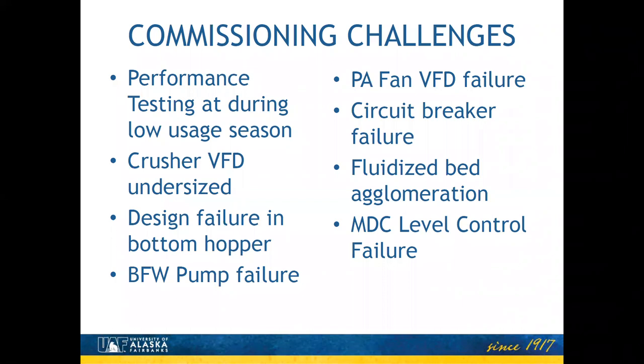Then shortly after that, we encountered a design flaw in the boiler. As explained in one of the previous slides, there's a big hopper at the bottom that contains sand and ash that makes the fluidized bed that the combustion takes place in. And this hopper had kind of a compound failure in it, one that in its design, it left out some fairly critical stiffeners in the steel to help it support its weight at the load points. And then the fabricator that made it had substituted lower grade steel and not notified anyone. So the two of those together resulted in a failure of the support beams for that hopper that took us a little while to get corrected.